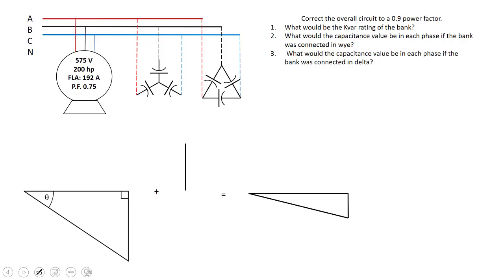In this case we've got a 575 volt motor, 200 horsepower and an FLA of 192 with a power factor of 0.75. The 200 horsepower isn't really valuable information here because that always refers to the power output of the motor and we don't know what efficiency this is operating at.